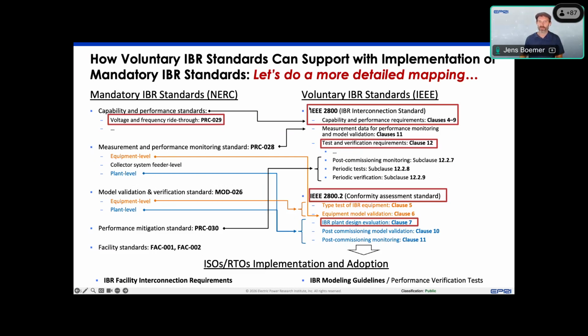And these red boxes try to do a little bit of mapping. So there are parts in IEEE 2800, the base standard, related to capability and performance requirements, particularly in Clause 7, that relate to ride-through, and the test and verification requirements in Clause 12 are then further detailed in IEEE 2800.2. And in particular, Clause 7 for IBR plant design evaluation. So to some extent, IEEE 2800 and 2800.2 could serve as a reference or technical inspiration for entities adopting these procedures, including IBR facility interconnection requirements and IBR modeling guidelines for performance verification tests by ISOs, RTOs, and other TOs.